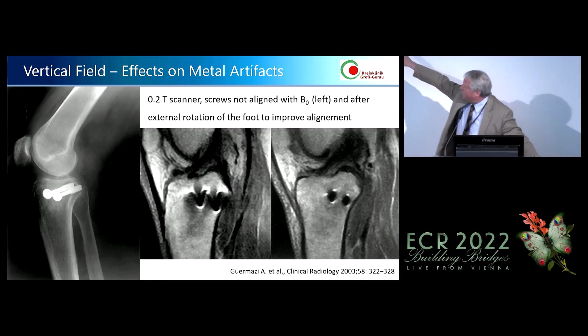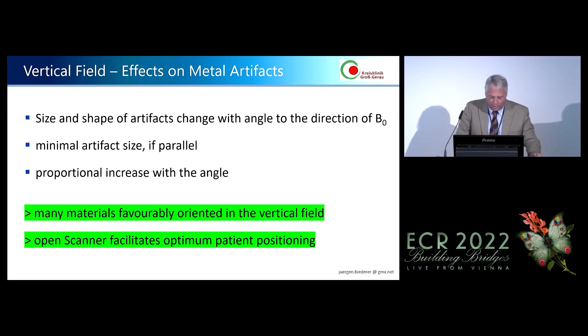So size and shape of artifacts change with the angle to the direction of the magnetic field. Minimal artifact size if it's parallel to the magnetic field, as we've seen. And with the angle, it gets worse and worse with the proportion of the angle. So many materials are already in the body favorably orientated to the vertical field, and the open scanner helps you to optimize patient positioning. You can work on that and make that optimum.